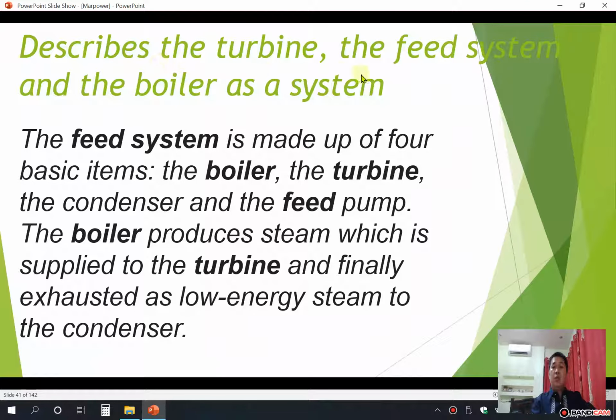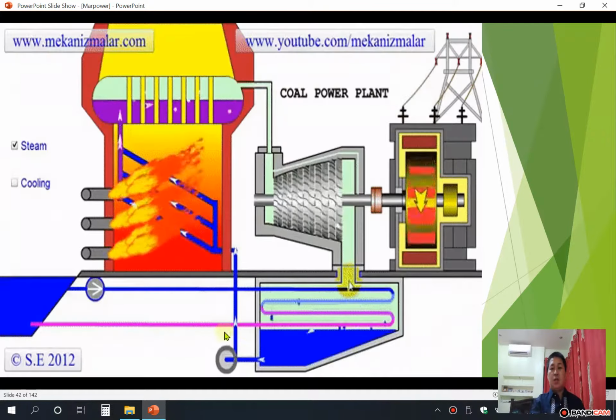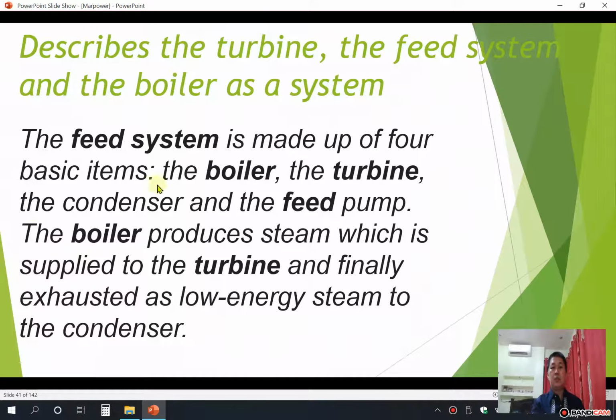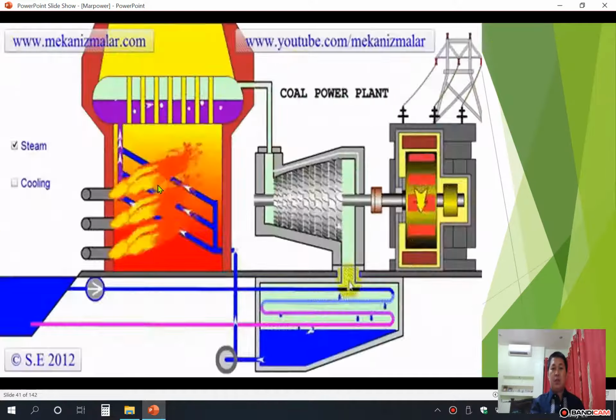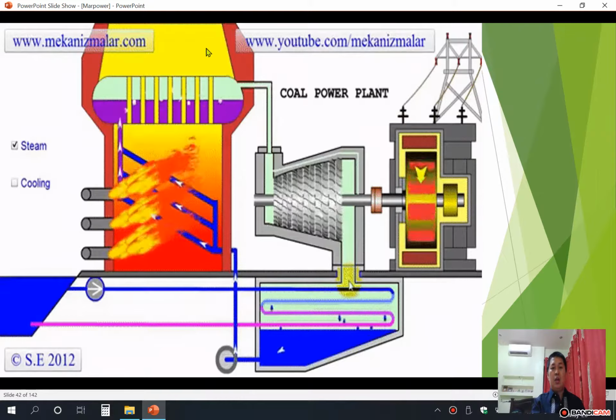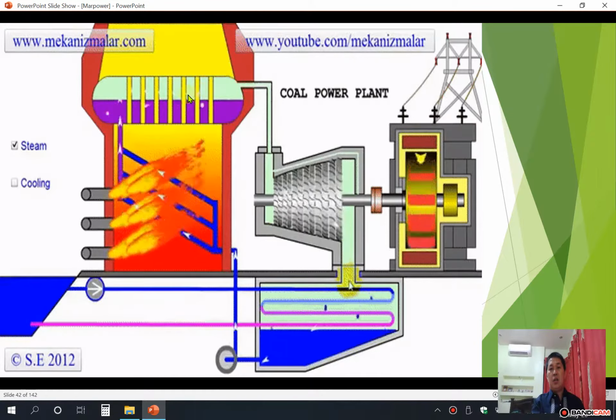Describes the turbine, the feed system, and the boiler system as a system. The feed system is made up of four basic items: the boiler, the turbine, the condenser, and the feed pump. The boiler produces steam which is supplied to the turbine and finally exhausted as low energy steam to the condenser. Say this is your turbine.